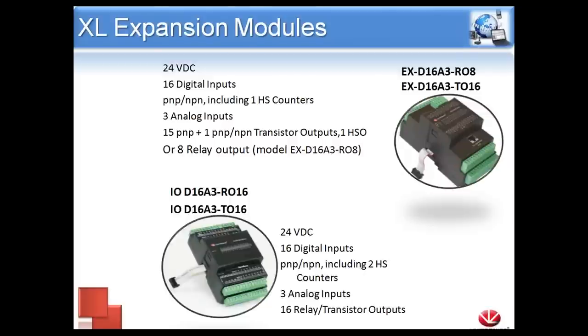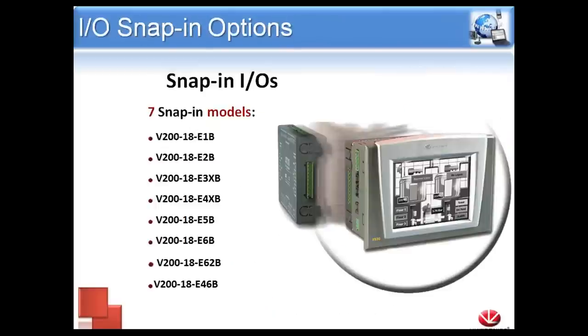We also offer the XL line of I/O adapters. They are high-density I/O modules with a larger grouping of both digital and analog inputs and outputs. The EX-D16A3-RO8 and the EX-D16A3-TO16 actually have the expansion adapter built in, so you do not need to get the EXA2X separately. If you're concerned about cabinet space, it might make sense to go with the high-density I/O, as we'll remove the EXA2X from the equation and have more I/O per square inch.